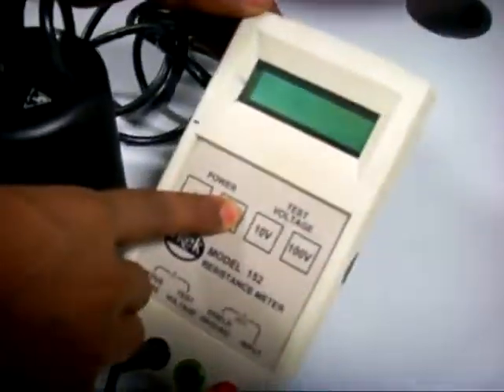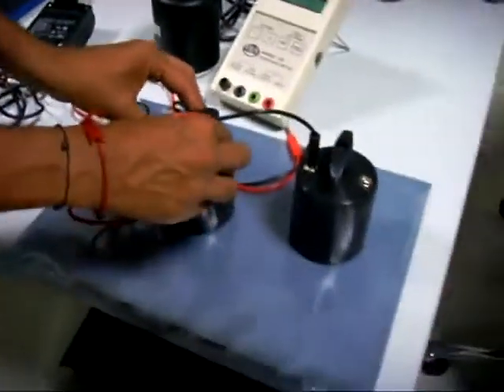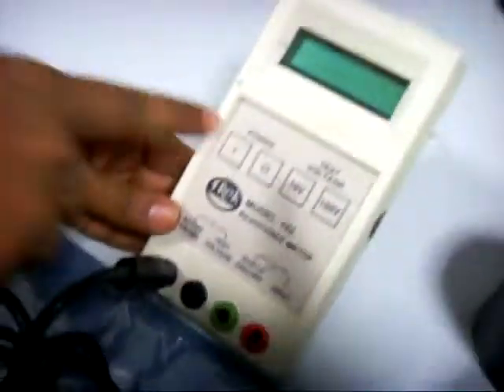And if you want to measure the surface resistivity, switch off. We are using the concentric ring probe to measure the surface resistivity of the material. We are selecting 100 volt. This is the surface resistivity, 1.6 into 10 power 10 ohms per square.